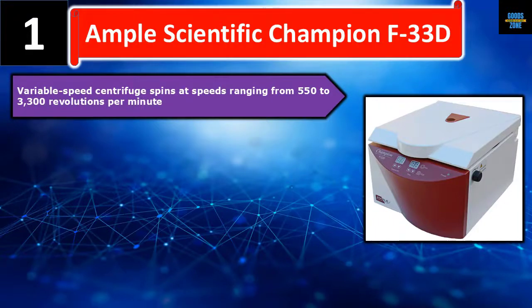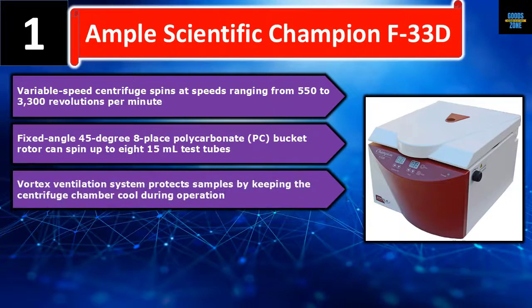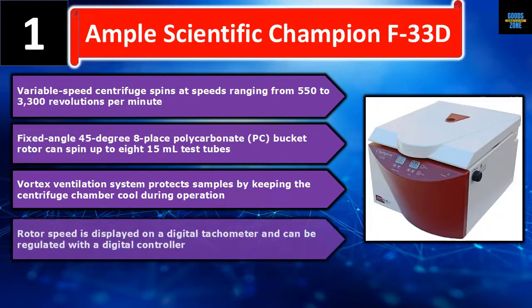It features a fixed angle 45-degree 8-place polycarbonate PC bucket rotor that can spin up to eight 15 mL test tubes. The vortex ventilation system protects samples by keeping the centrifuge chamber cool during operation. Rotor speed is displayed on a digital tachometer and can be regulated with a digital controller.